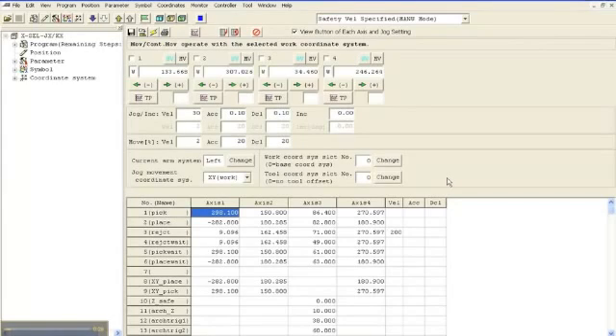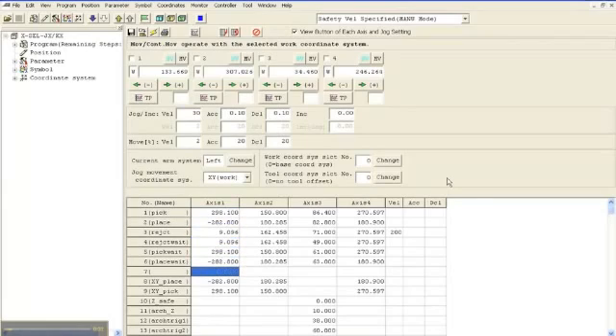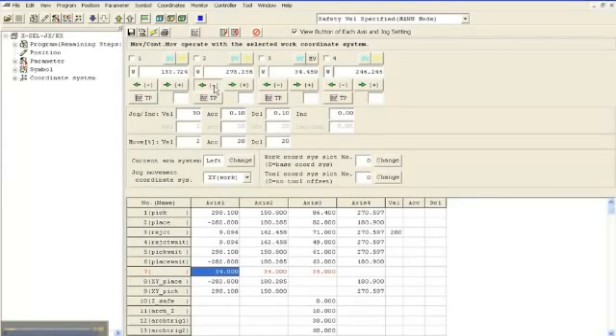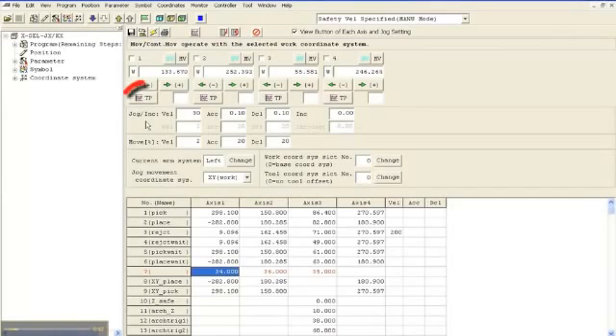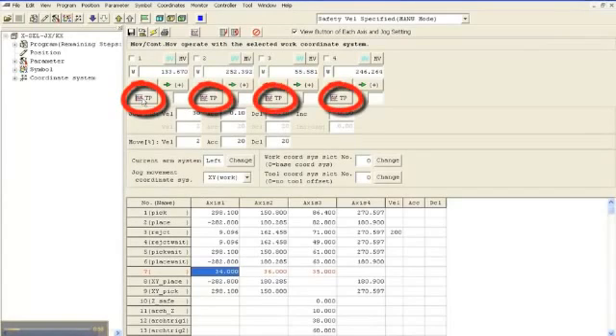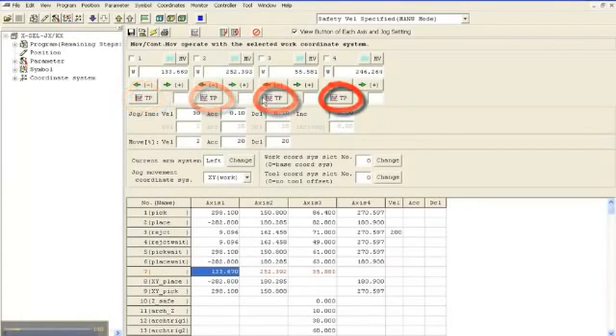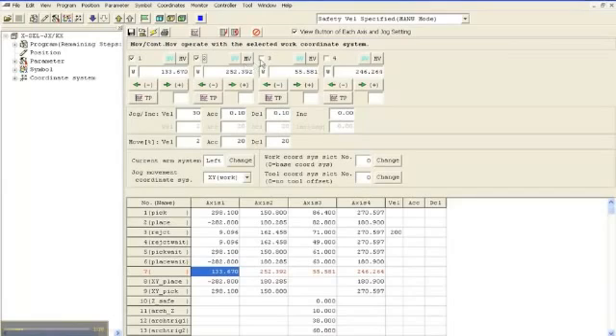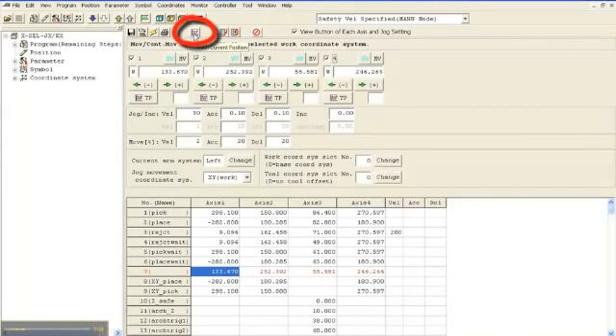Teaching positions is easy. You can do it one of three different ways. The first method is to simply type in the axis information for each individual axis. The second method is to turn the servos on and jog the actuator to the location that you want to teach. Once you have the actuator in the correct location, you can teach the information one of two different ways. There is a Teach Current Position button under each axis. When you press this button, it will grab the current location of that axis and store it inside the position table. The second method is to click the check box next to each axis that you would like to teach. When the boxes are selected, you can press the Teach All button up at the top of the screen.